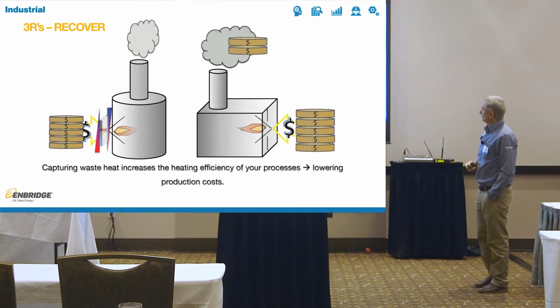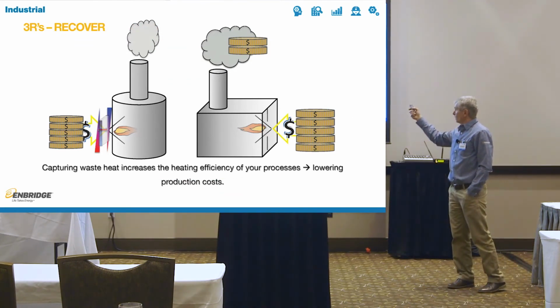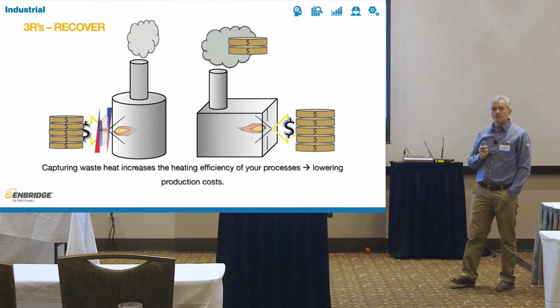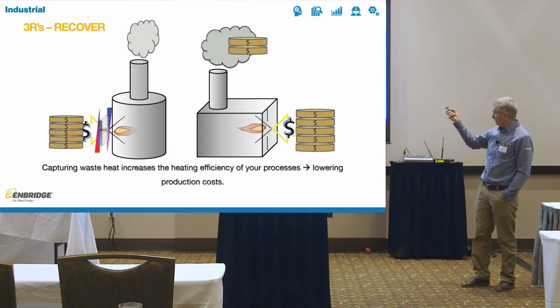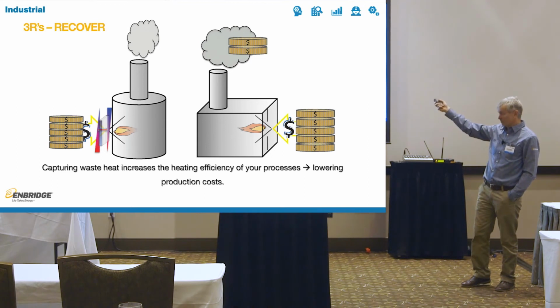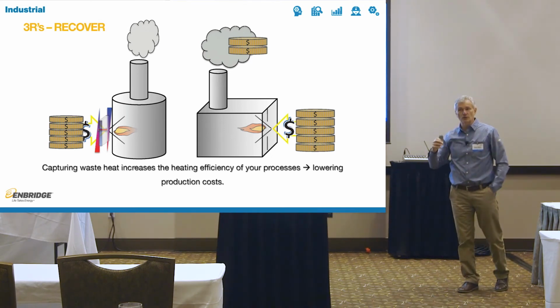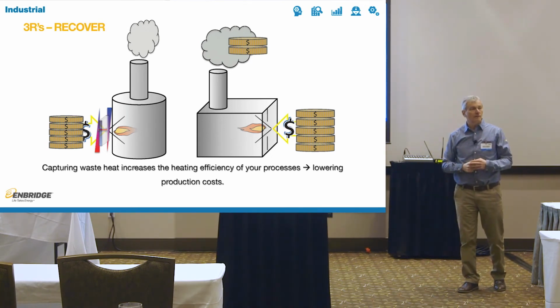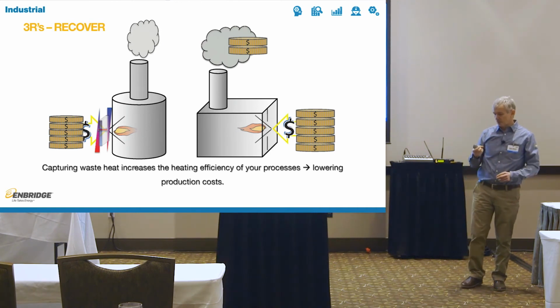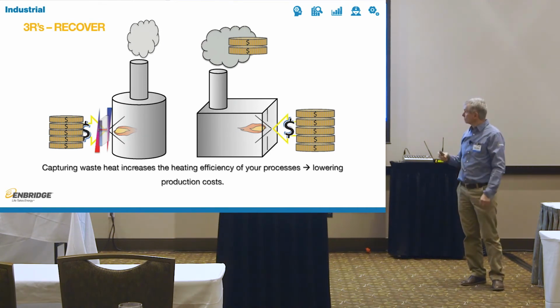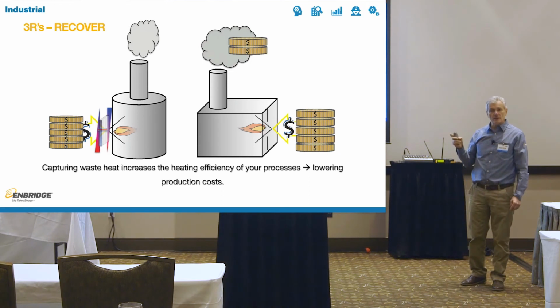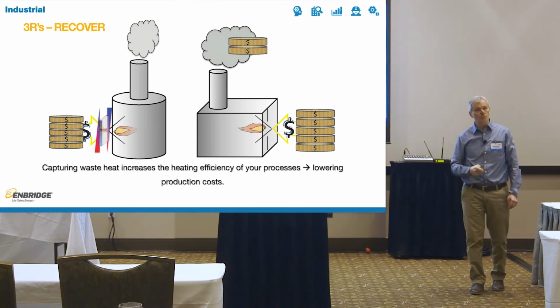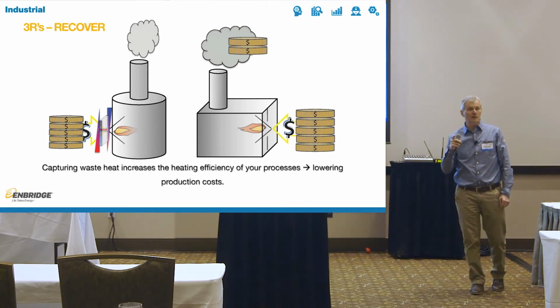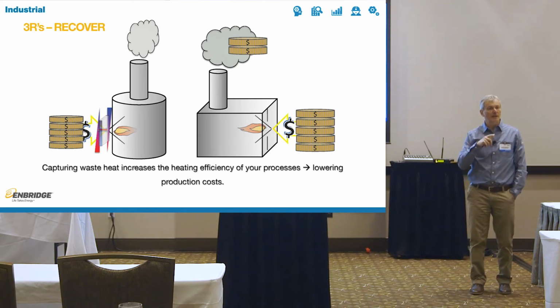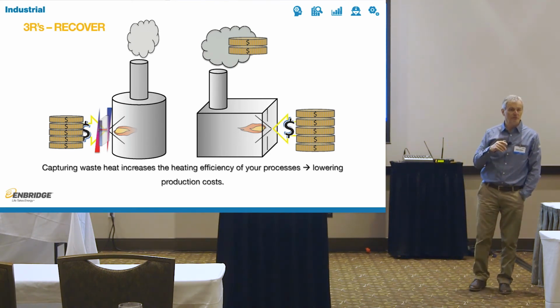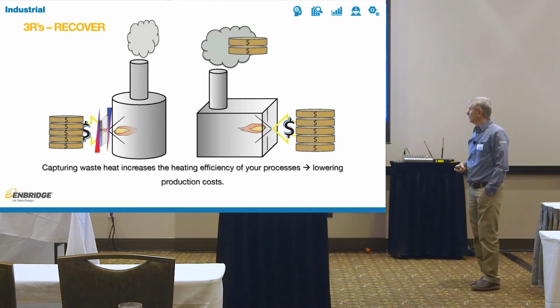Another way to recover heat, if you have a boiler and a water heater of some sort. One of my favorite examples, because this water heater, for example, was a direct fired water heater, direct contact water heater. Everybody will tell you 99% efficient, all sorts of stuff. But in their particular case, it was going into the loop. So the direct contact water heater wasn't actually giving them any benefit. They were running at about 55% efficient when they actually looked at it.